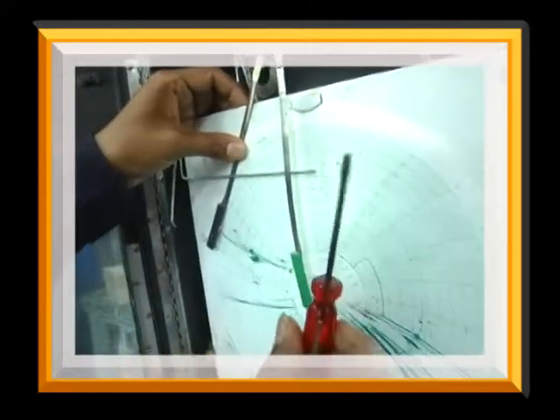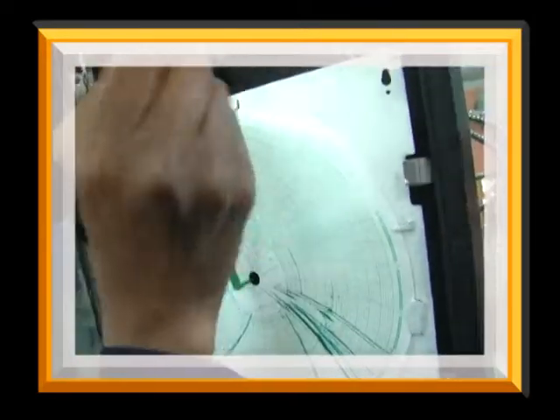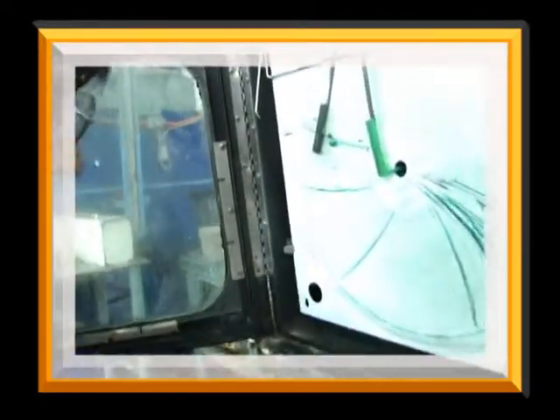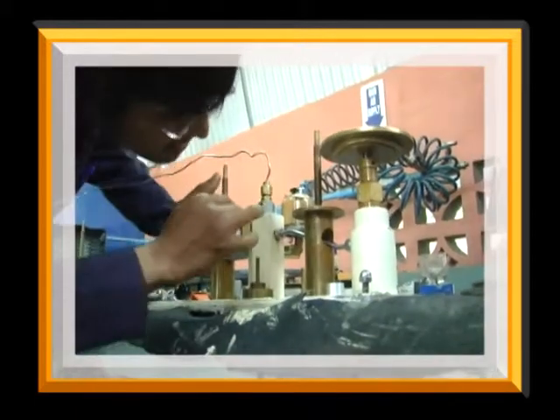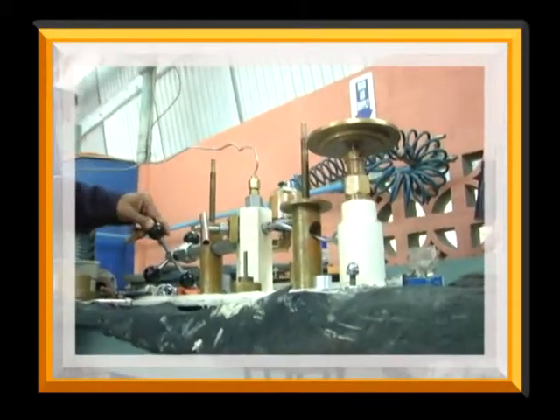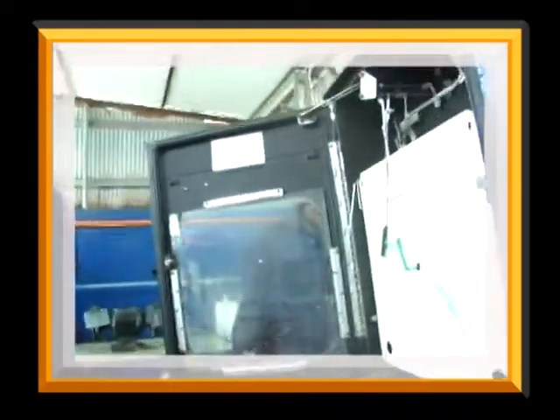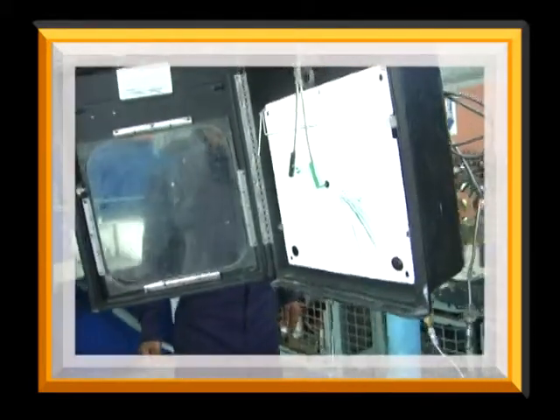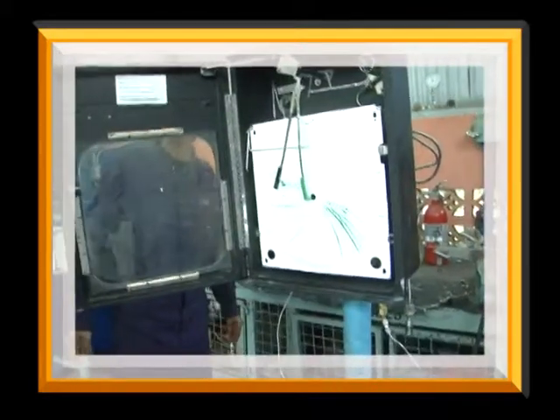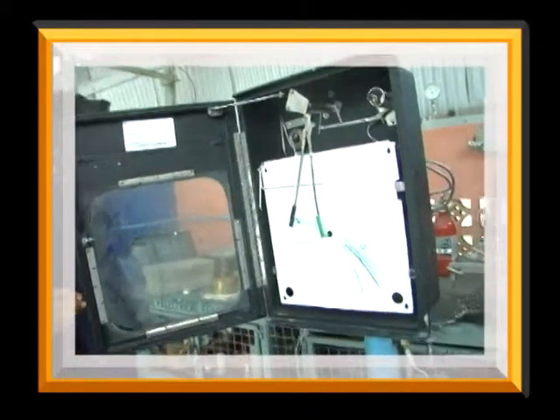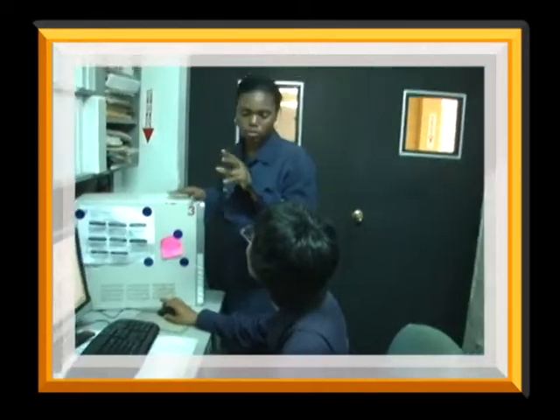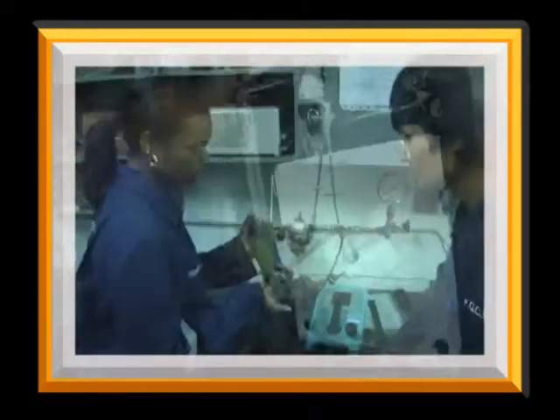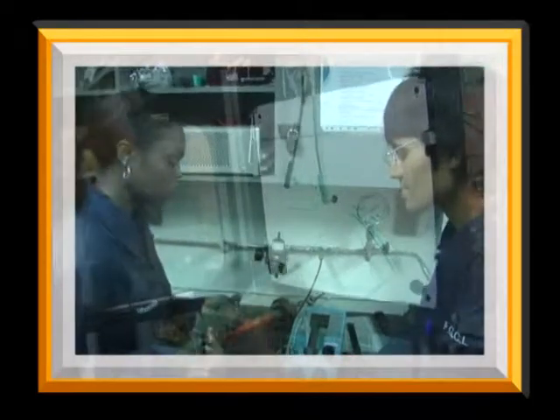Adjustments are made using the reference meter applied pressures, ensuring it compares with the indication on chart. All steps are repeated until all of the 3 points, 0, 50, and 100% indication are achieved. To assure the accuracy of the unit, an 11-point calibration check is carried out. On completion of the job by the E&I technician, verification is made by the quality control technician, ensuring that the work was done by the written procedures.